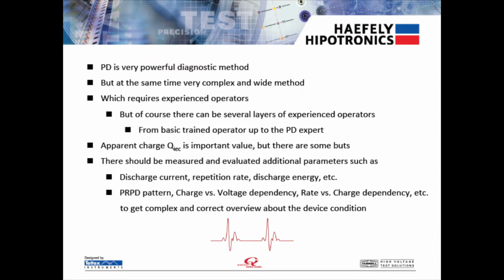So PD is one of the most powerful diagnostic methods available. This is because it's observed early on in failures and gives you a heads up if something is starting to go wrong in the transformer. Nevertheless, it's a complex method. There's a lot of information that needs to be analyzed. Because of this, we recommend that operators be very experienced.